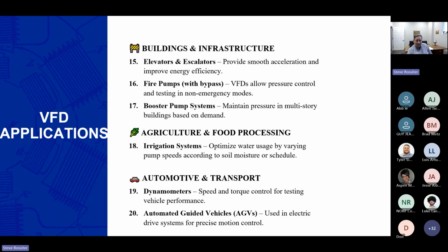When we talk about some of these applications, I'm reminded when I was in New Zealand, I saw almost all of the irrigation there was done by submersible pumps, where here in the West, at least in the US, it seems like everything is a vertical hollow shaft turbine pump. When we get into submersible pump applications, it's, for me, very important that we look at the length of wire between the drive and that motor, and especially when it's not in a media of air as an insulator, but in water. We almost always apply sine wave filters because the effect on windings is even more detrimental in that application where it's in a submersible well. Dynamometers, of course, I've mentioned, even vehicles. Every electric vehicle is based on variable frequency or inverter technologies.